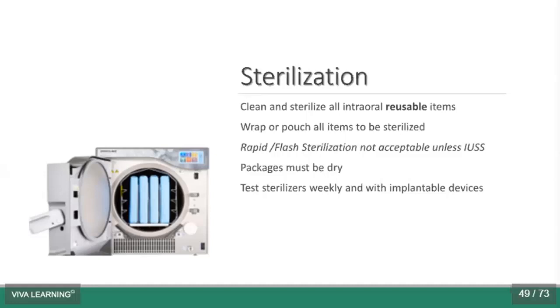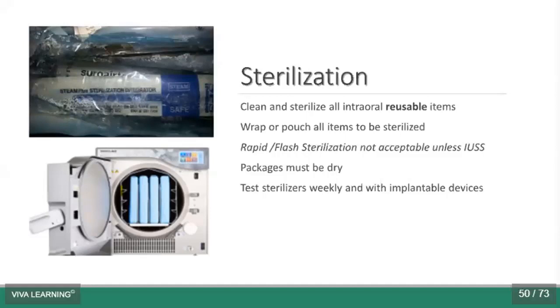Those packages must be dry when they come out of the sterilizer, right? Every single sterilizer manufacturer that I've talked to said that if the instruments are coming out wet, there's a problem with the process, right? It's either a problem with the sterilizer, or most likely it's operator error. We've overloaded the sterilizer, or we have too many instruments per pouch, or we didn't let it go through the dry cycle is the most common reason I hear.